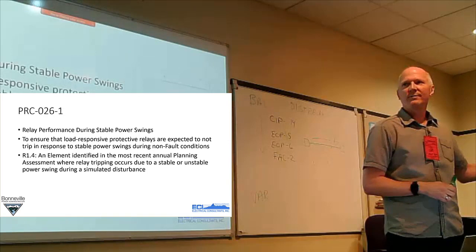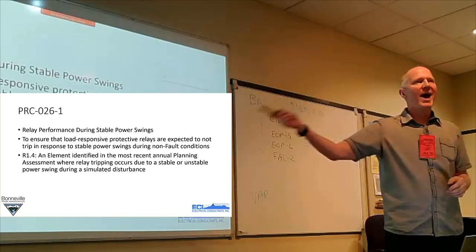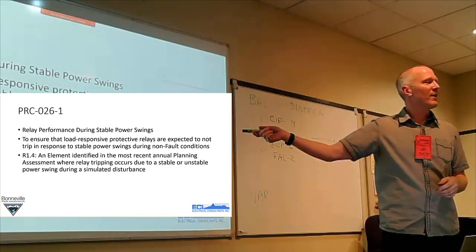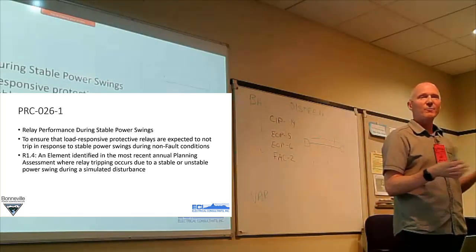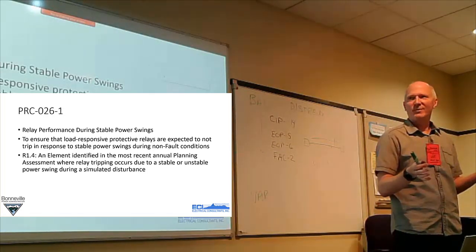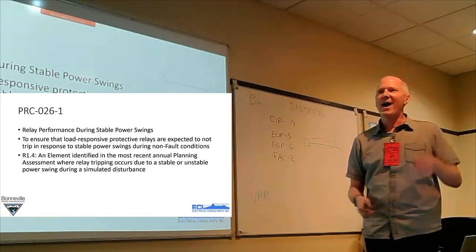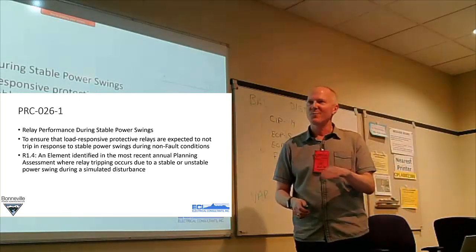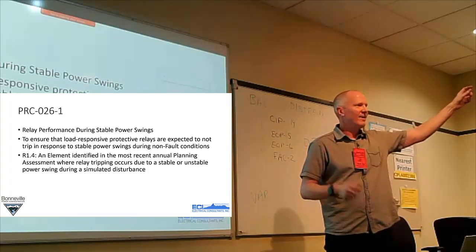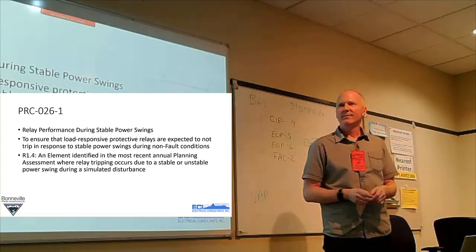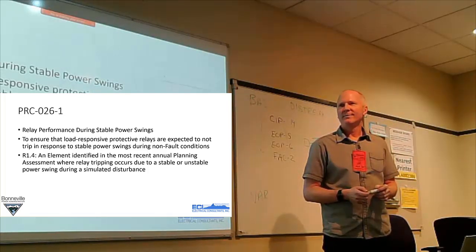It really does. Yet your simulator tool has the capacity, at least for some of the folks that we've done work for, I've put them in and said, hey, none of them tripped where they shouldn't have tripped. And there might be an easier way to do it. I had to look at event logs to look for it. There might be a more programmatic way to see, did that distance relay over here play for the fault over here? Yeah, we don't have anything. You'd have to do what you do.